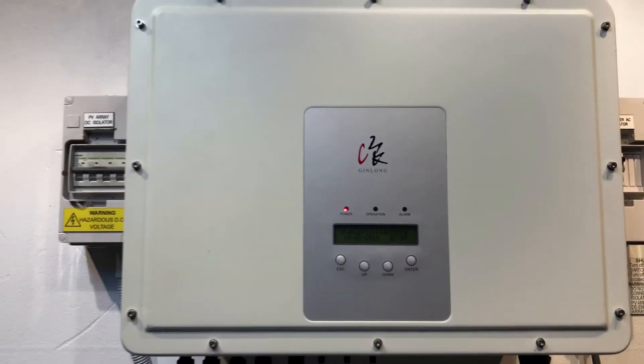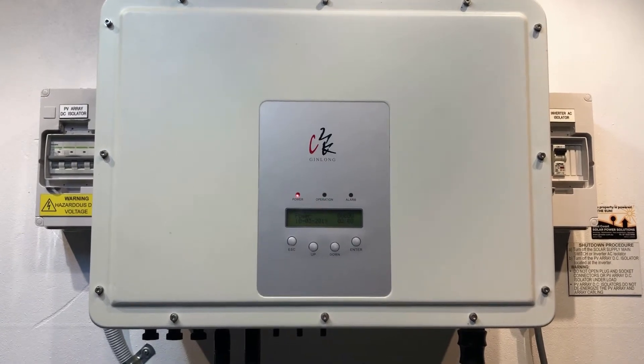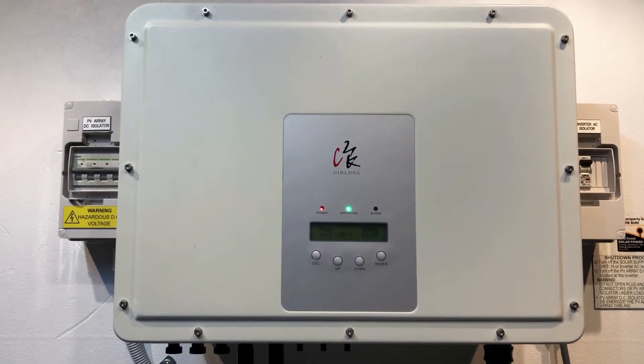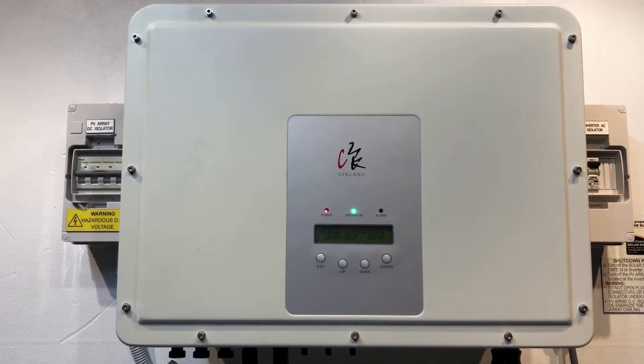So if your inverter after five minutes is still stuck on initializing and producing zero watts, it is an issue with your inverter. The Ginlong inverters came with a five-year warranty, so you can potentially get it replaced under warranty if it's within the five years.